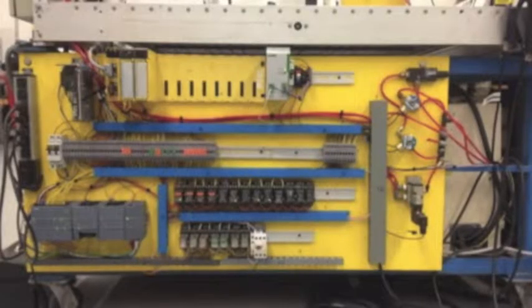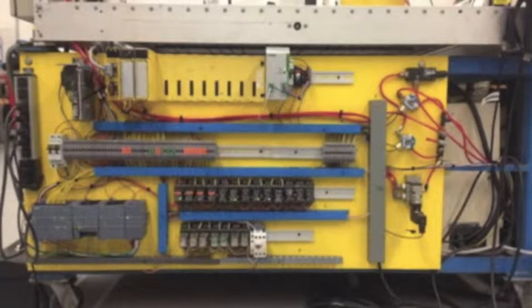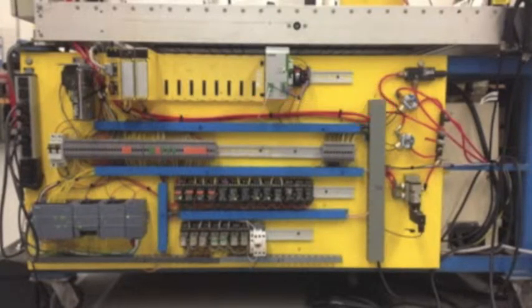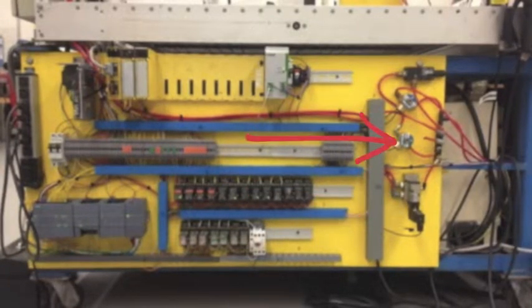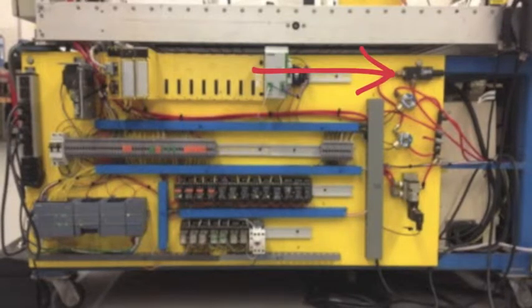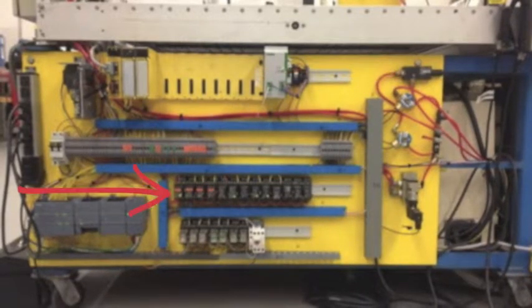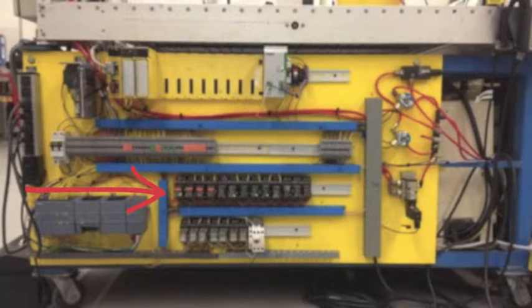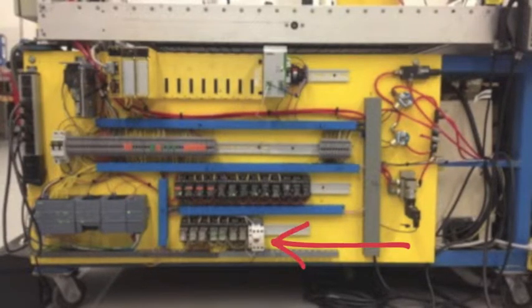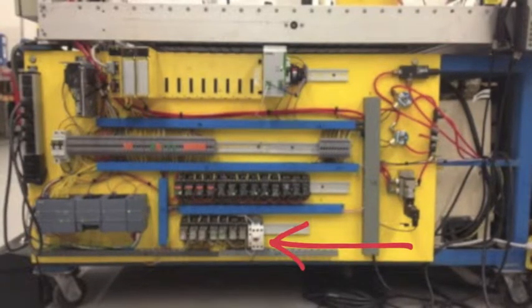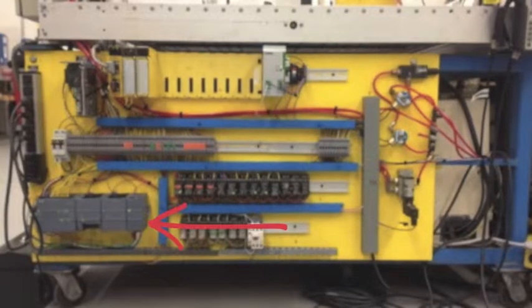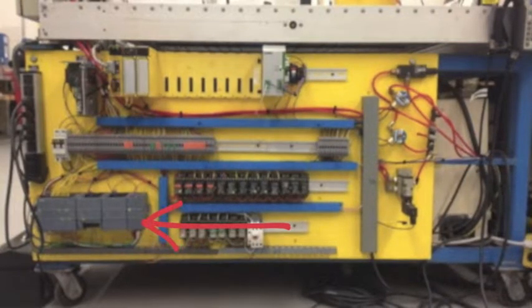This board is a combination of a relay and valve board. 3 valves are used, one for main air, one to extend the welder cylinder, and the third goes to the vacuum generator controlling our suction gripper. Here's our MCR, and all of our crosstalk relays, and a contactor for the welder, due to the amount of amperage drawn while welding. This is our Siemens S7-1200 CPU and I/O modules.